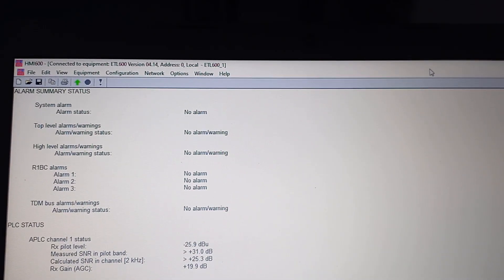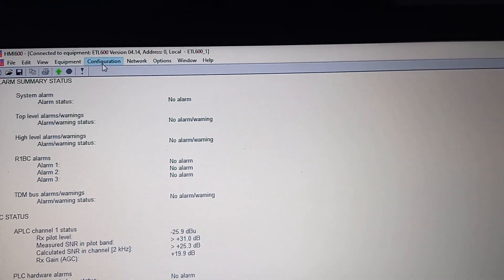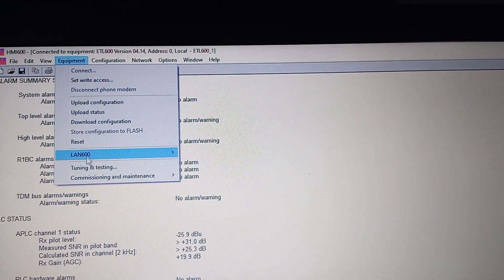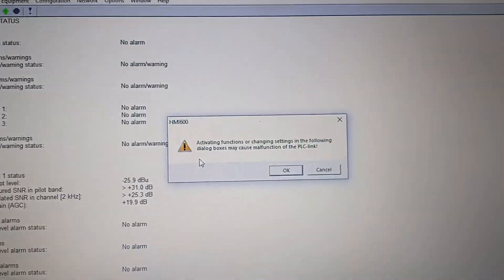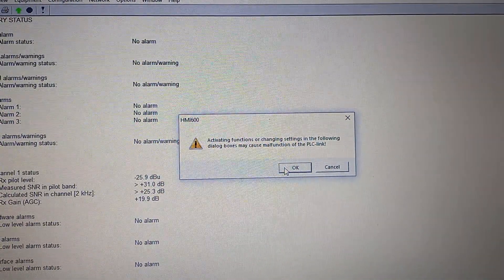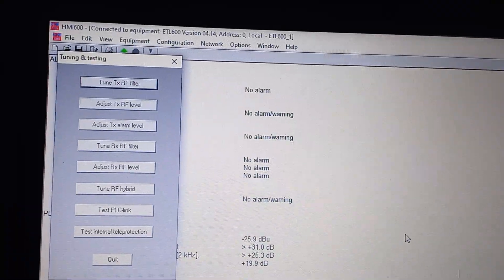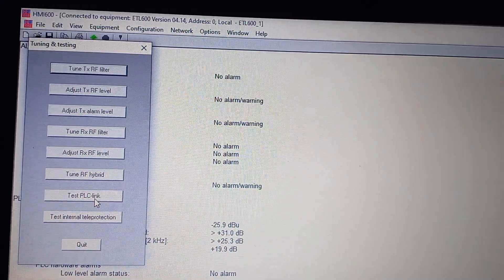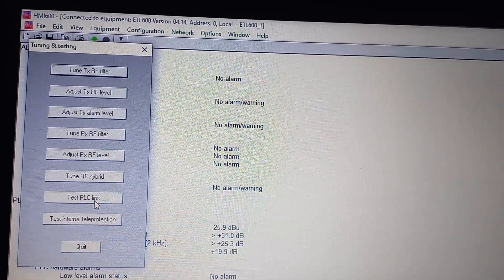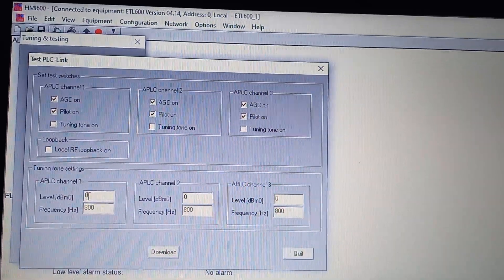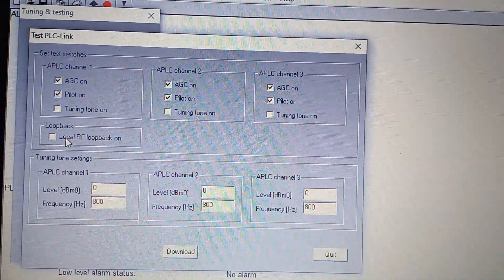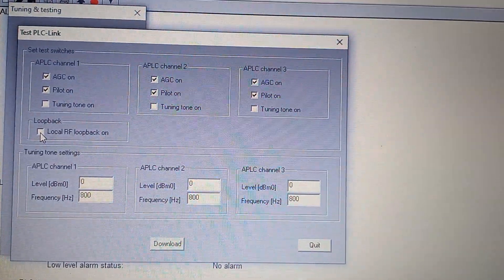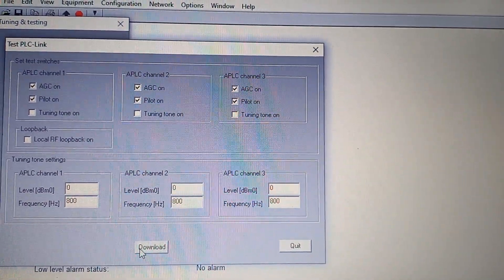After that, a summary window will open. Go to Equipment, then Tuning and Testing — you will get a message, click OK. Here you can see the Test PLCC tab. Click on Test PLC Link. Here you can see the Local RF Loopback option — just select it and download if you want to put this PLC channel in local mode.